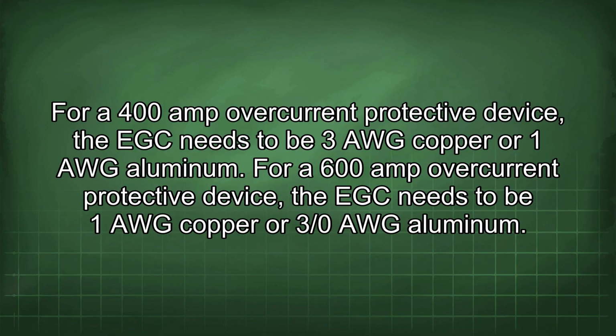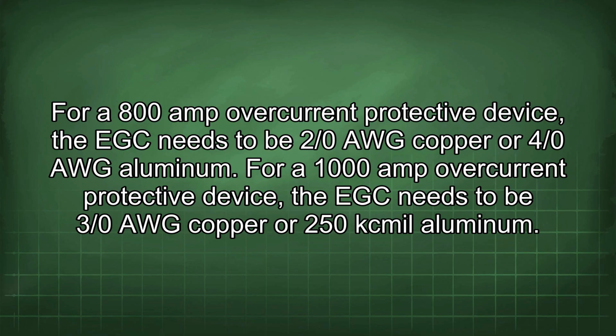For a 400 amp overcurrent protective device, the EGC needs to be 3 AWG copper or 1 AWG aluminum. For a 600 amp overcurrent protective device, the EGC needs to be 1 AWG copper or 3/0 AWG aluminum. For a 800 amp overcurrent protective device, the EGC needs to be 2/0 AWG copper or 4/0 AWG aluminum.